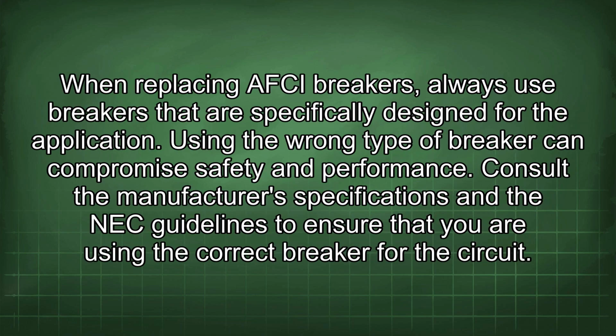When replacing AFCI breakers, always use breakers that are specifically designed for the application. Using the wrong type of breaker can compromise safety and performance. Consult the manufacturer's specifications and the NEC guidelines to ensure that you are using the correct breaker for the circuit.